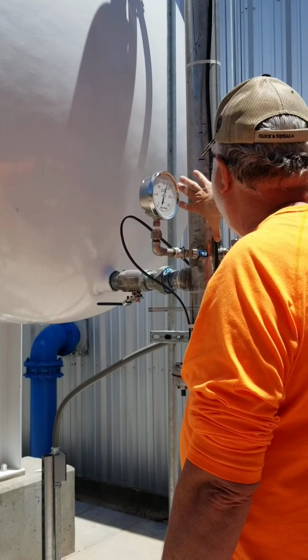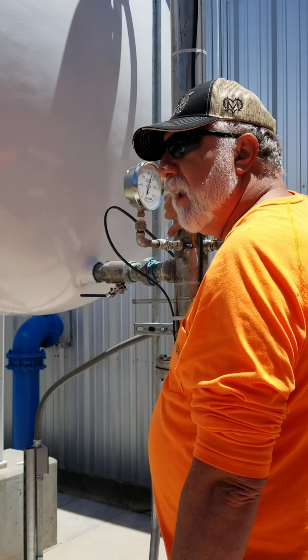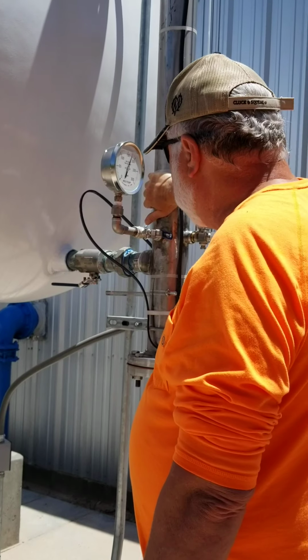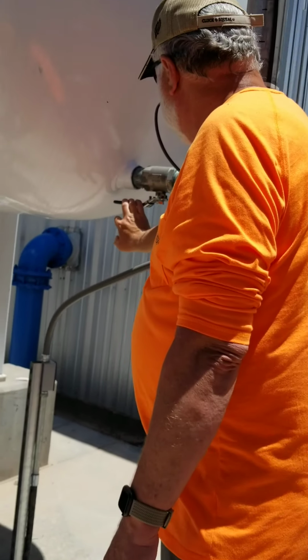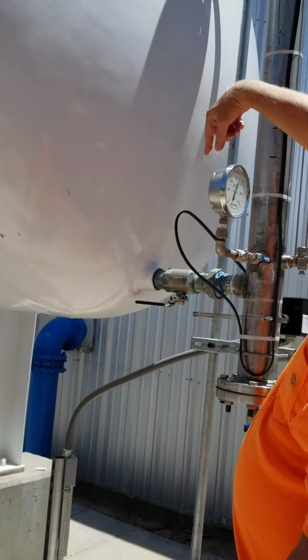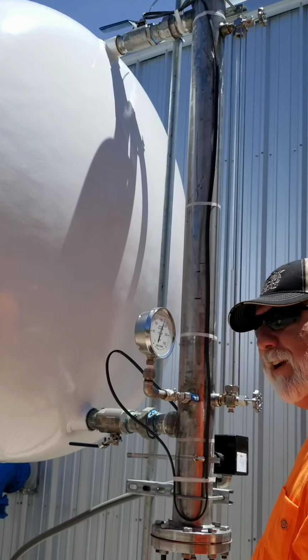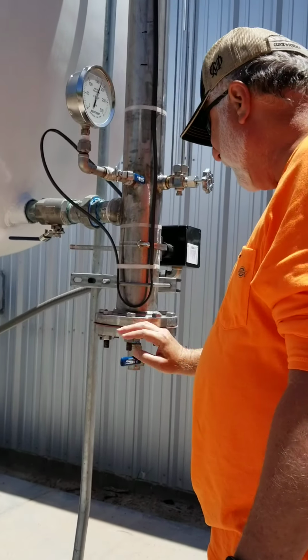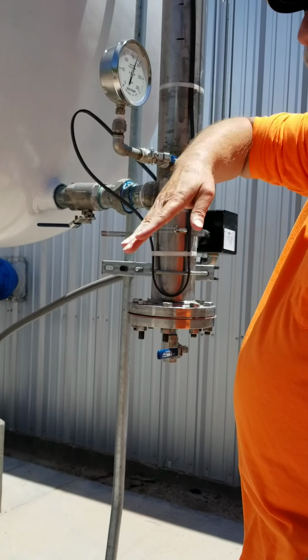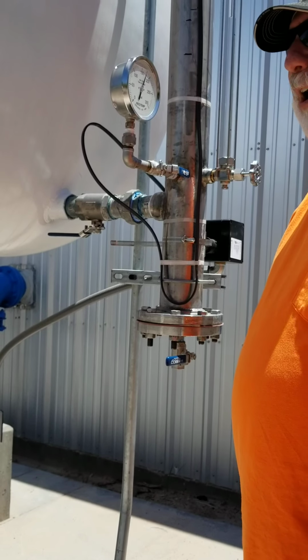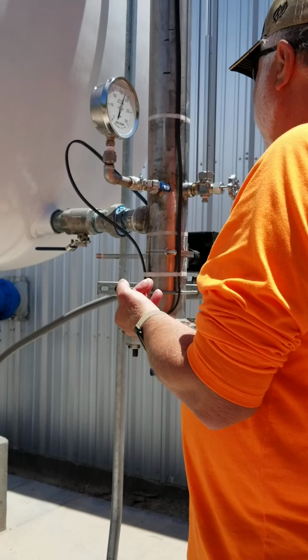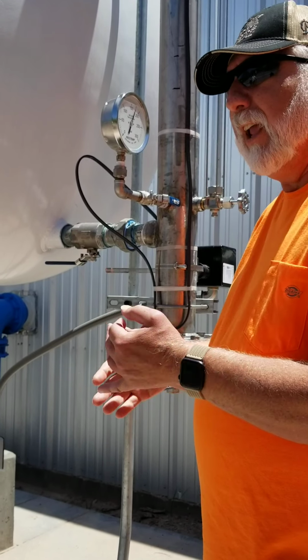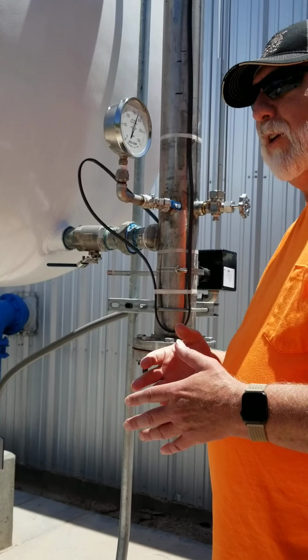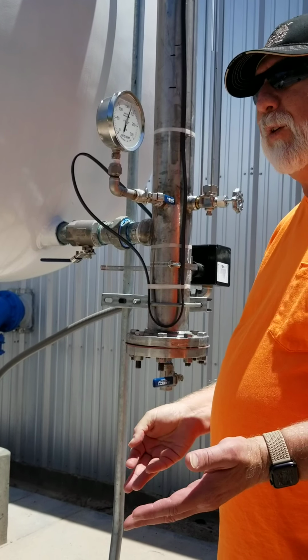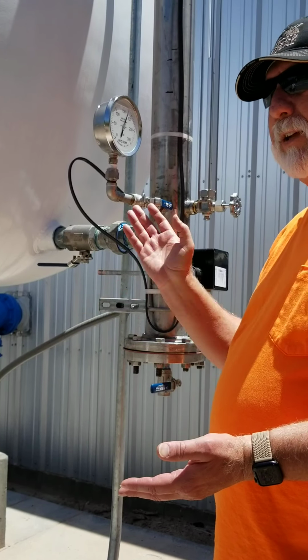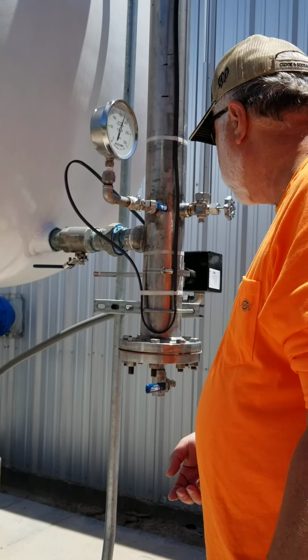One nice thing about having it in a probe bottle off the side of the tank, you can always test your system. If you close the isolation valves at the top and the bottom, drain it all off, close it, you can open this and move that water level anywhere you want in that tank. That way you can test your probes, you can test all your other sensors, and you have a way of looking at your system to make sure everything's functional without having to take it out of service, because it can still be running during that entire process.